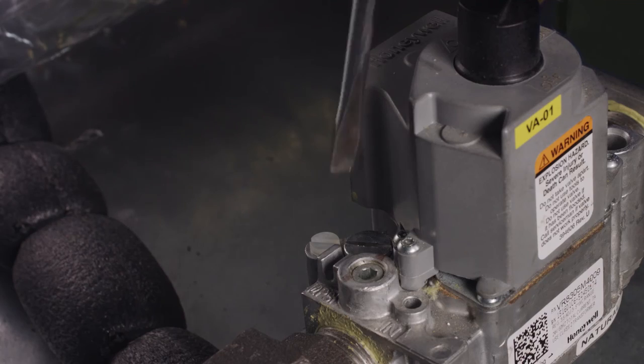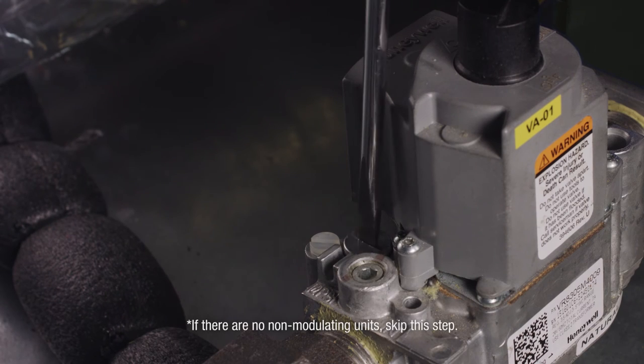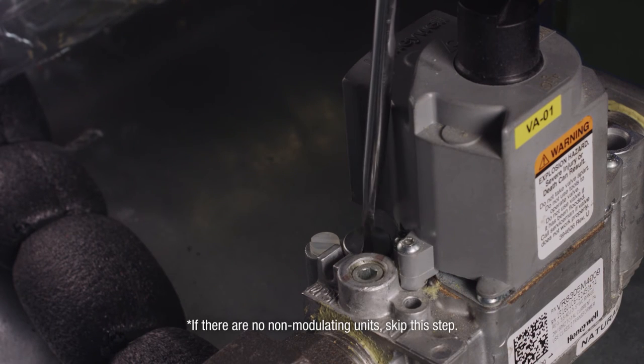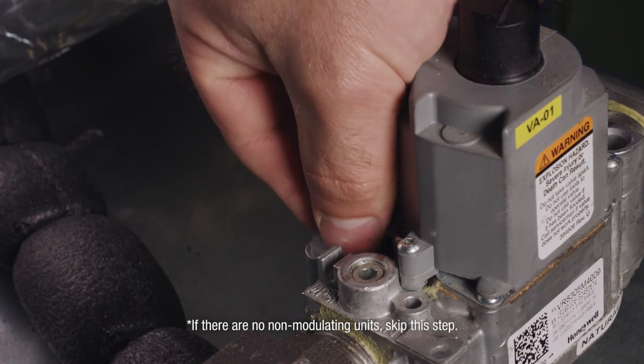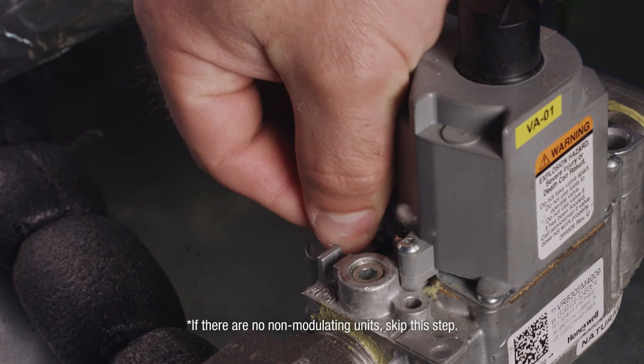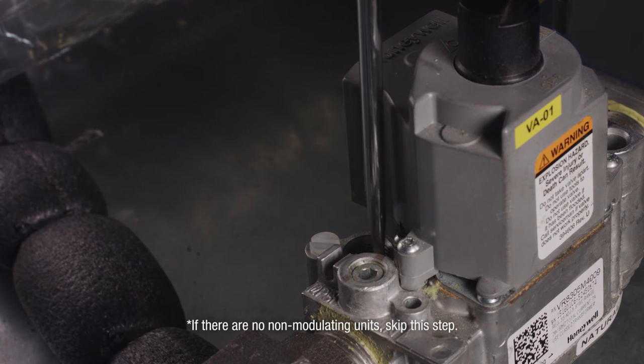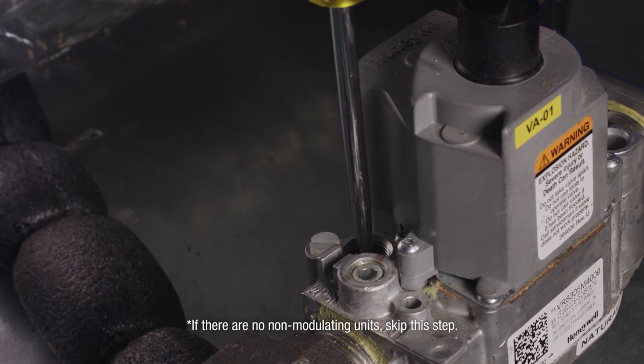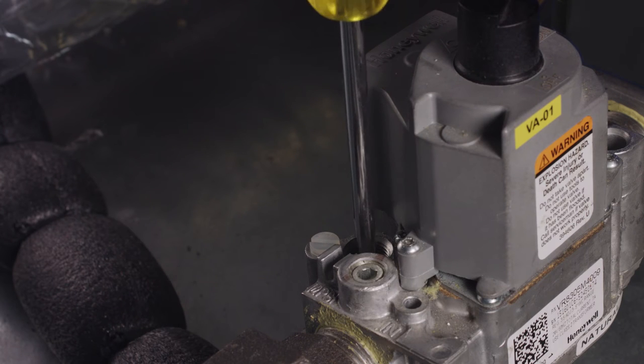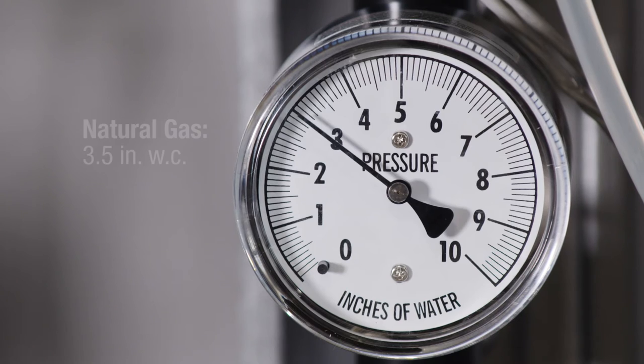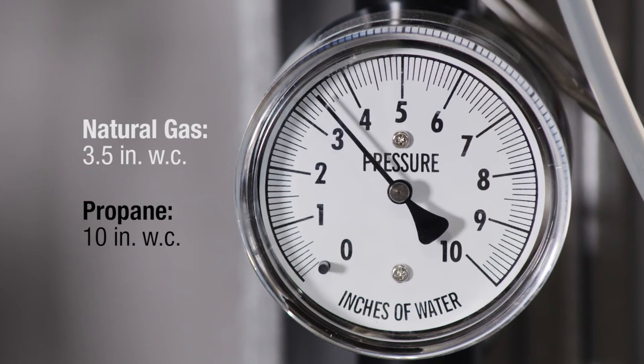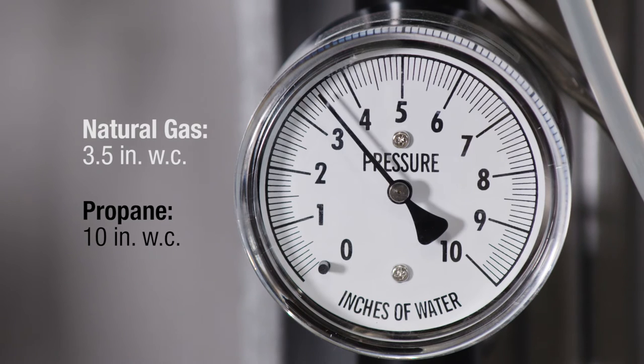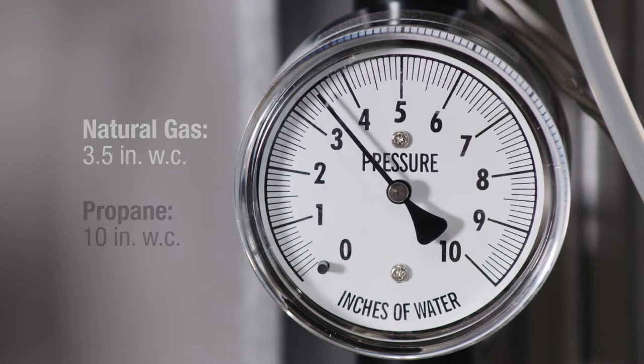With all burners lit, set the manifold gas pressure on the non-modulating stages if present. Turn the inner adjustment screw clockwise to increase the gas pressure and counterclockwise to decrease pressure. Pressure should be adjusted to equal 3.5 inches water column on natural gas and 10 inches water column for propane.